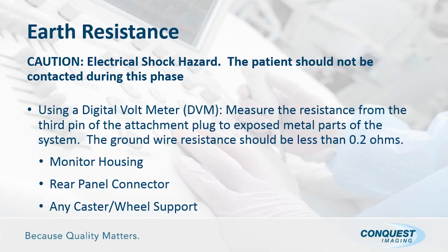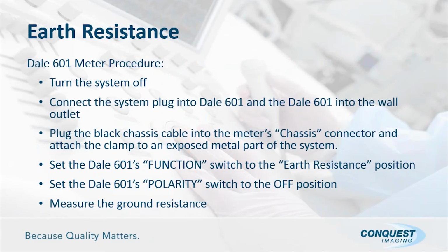They tell you to check it in 3 places: from the monitor housing, where there's exposed metal, the rear panel connector, and any caster or wheel support that has metal on it. So it's not just good enough to do one spot on the system. They want you to check multiple spots. And then we talk about the same reading, but instead of using a digital voltmeter, we use the Dale 601.